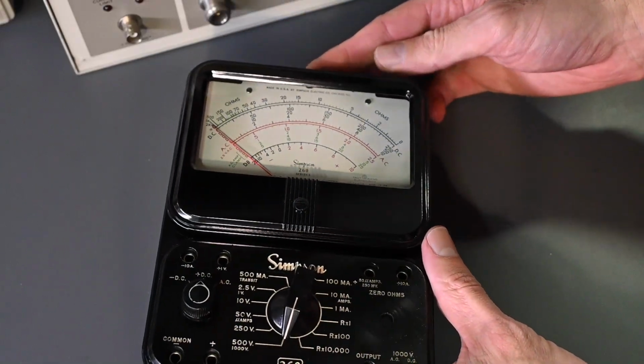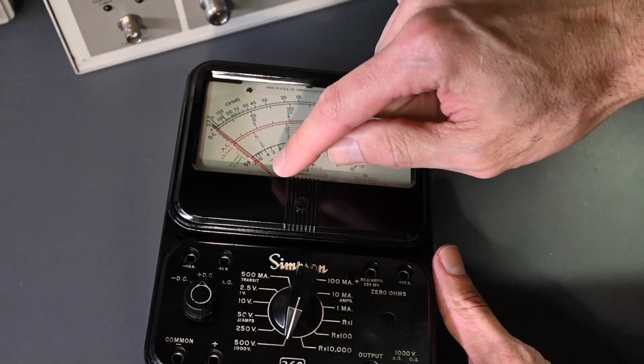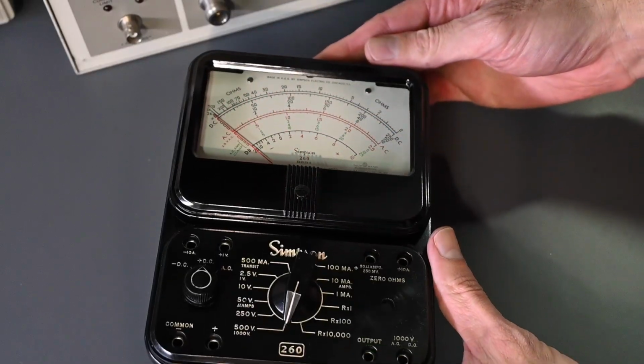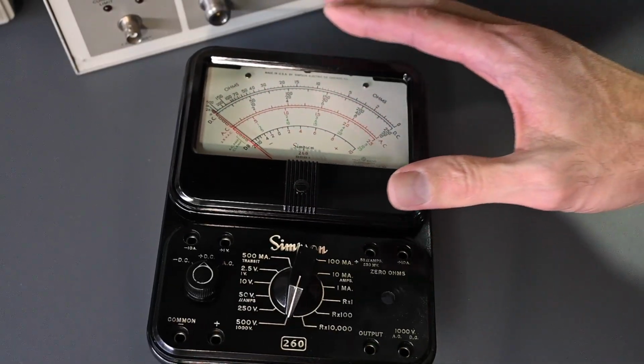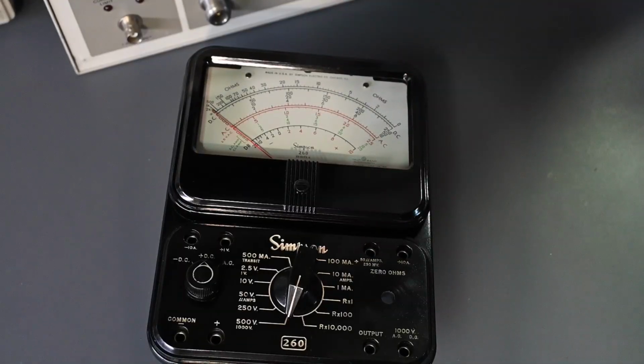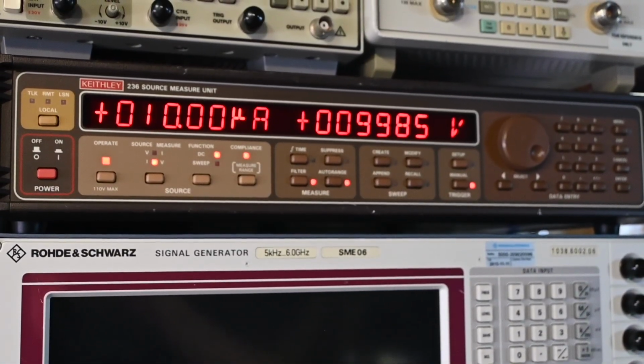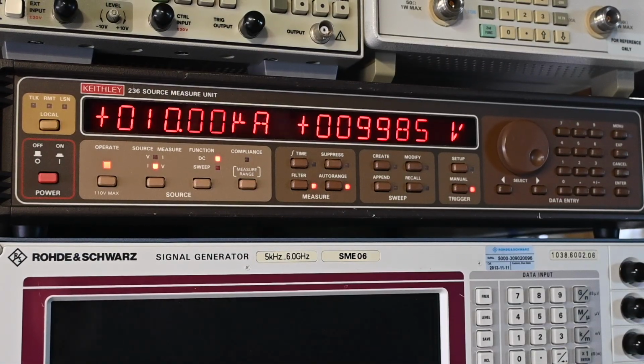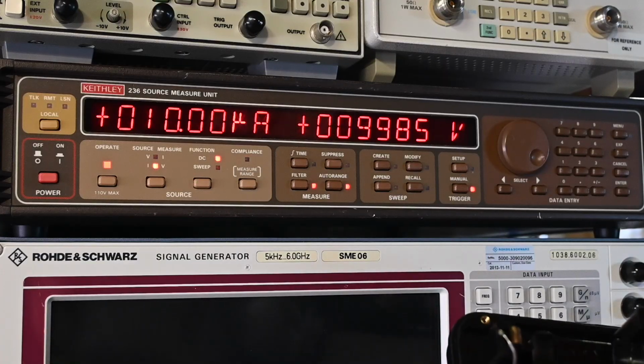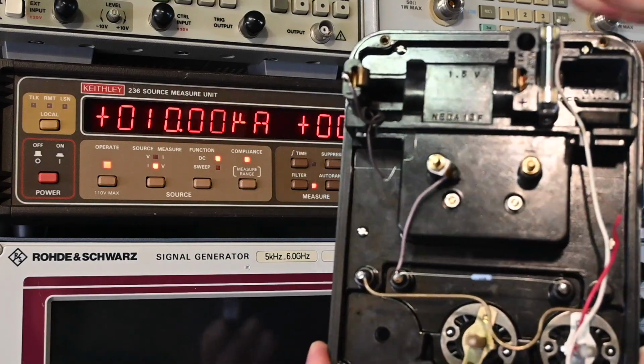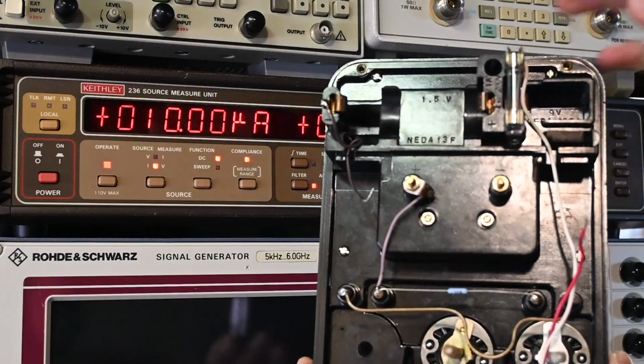And I have this zero adjustment set, so the needle is resting right on the 0 point. So the next thing I want to do is check the movement of this meter, and to do that, I'm going to move the camera up here, so pardon the camera movement. For this test, and also for the DC calibration, I'm going to be using this Keithley 236. I'll talk a little bit about this in just a moment. The first thing I want to do is check this meter movement, and on the back of the meter, the two terminals right here and right here, those go directly into the meter movement.